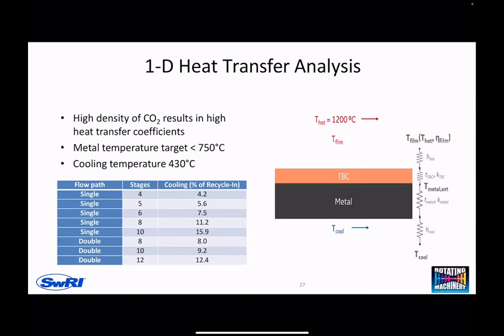Our main target here was to maintain a metal temperature target of around 750 Celsius. This is really when a lot of these high nickel alloys start to have creep issues or creep limitations in material properties, so I chose 750C. That gives us significant margin on stress, because these are going to be small blades, highly loaded from external pressures, so we really are going to have some high mechanical stresses.